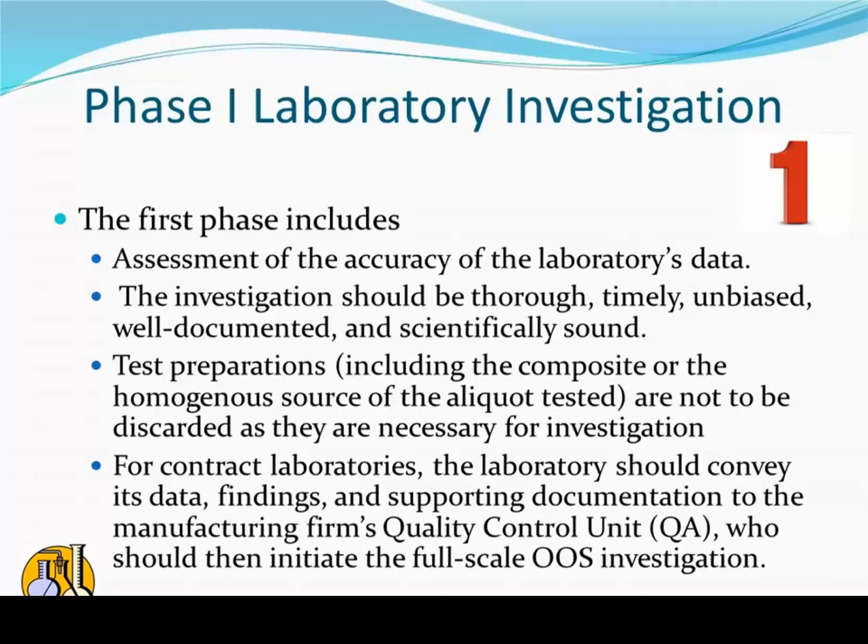Sally's been testing pH for quite some time. Her training is up to date. She gets lot 1, 2, 3. She decides to send it through the pH meter, and she gets a result of 6.9. So it's a little bit acidic, more acidic than we'd like. She immediately consults her standard operating procedure, and this is now called her original, first result.